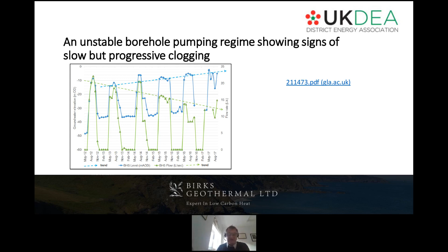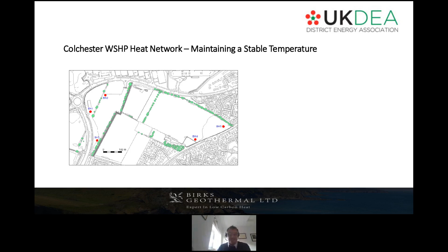So at Colchester Gateway, this is what the configuration looks like in plan. There are 2 abstraction wells, 3 reinjection wells, and about 600 to 700 meters between abstraction and reinjection. That distance is what I believe is needed to maintain a stable water temperature for at least a period of 5 to 10 years before we can start to balance heating and cooling, and that's important.